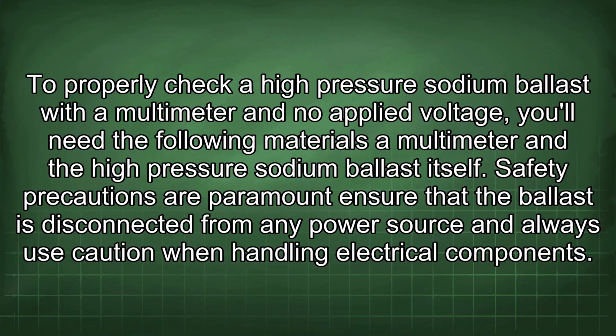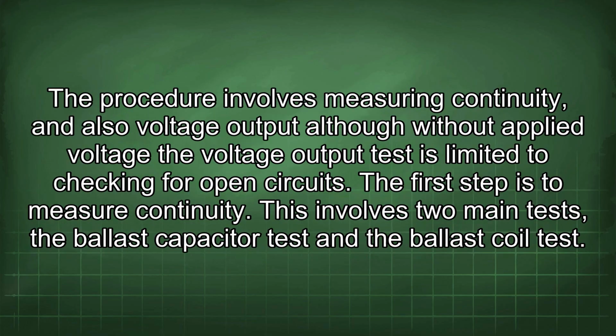To properly check a high-pressure sodium ballast with a multimeter and no applied voltage, you will need the following materials: a multimeter and the high-pressure sodium ballast itself. Safety precautions are paramount. Ensure that the ballast is disconnected from any power source and always use caution when handling electrical components. The procedure involves measuring continuity and also voltage output, although without applied voltage the voltage output test is limited to checking for open circuits.